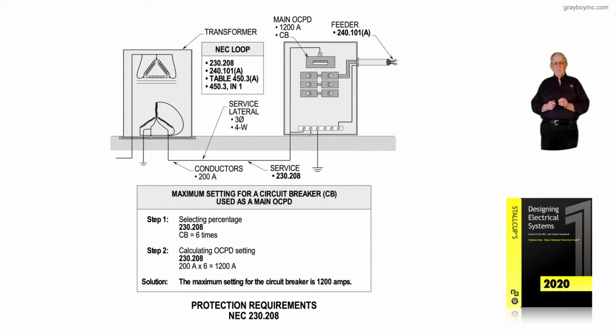Now, what they're saying here, if those underground conductors are 200 amps rated each, we could apply 230.208 in step 1 for a circuit breaker and size it at 6 times 200. Notice a 200 amp circuit breaker times 6 is 1200 amp setting.